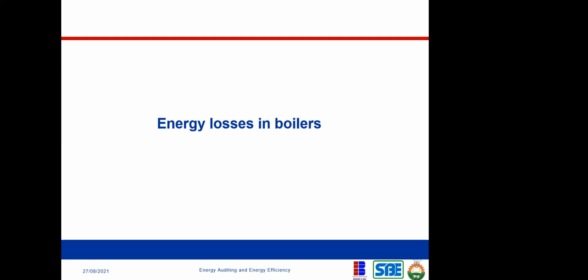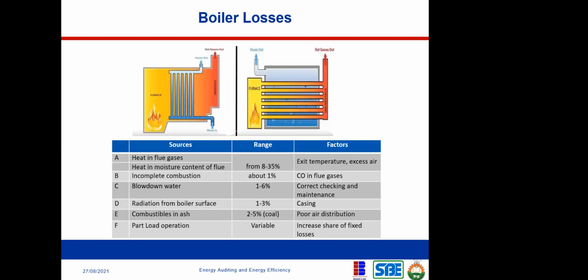So let us look at energy losses in boilers. Now we've talked about boilers and the principles, how boilers operate. Now let us look at how energy losses occur in boilers. So back to our two types of boiler. Here on this column, you're going to see the sources of energy loss. In this range, you're going to see the estimated percentage of losses that are occurring as a result of these sources. And here you're seeing factors, okay?